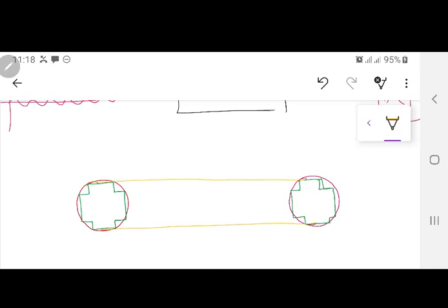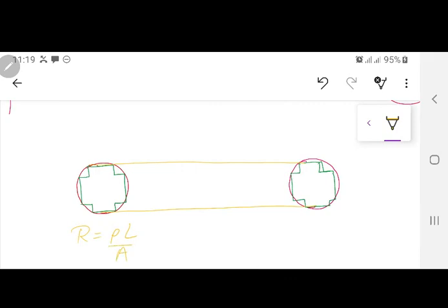If you had a square core, you would have a larger perimeter. So making it circular, maybe 2-step, 3-step, 4-step or up to 11-step, you are trying to reduce the length of your winding. And reducing the length of the winding, we know, since R equals rho L over A, reduces the resistance.